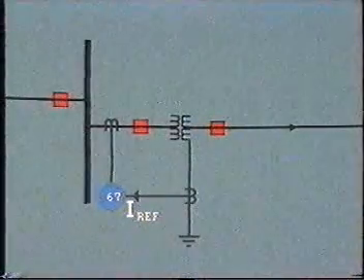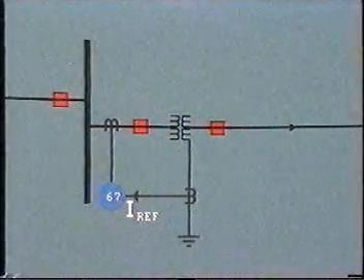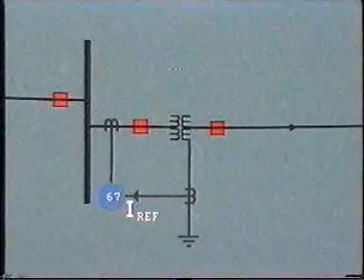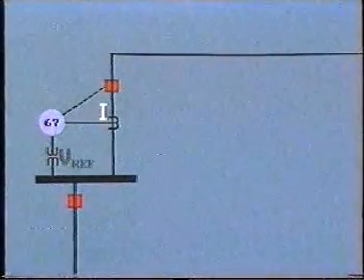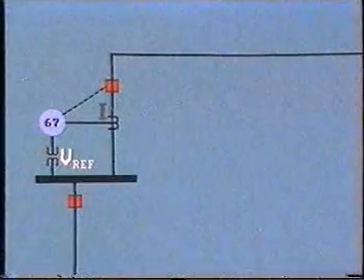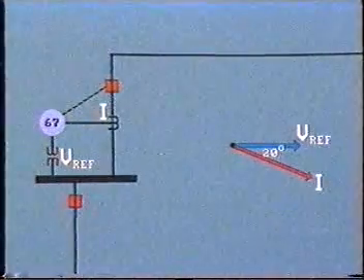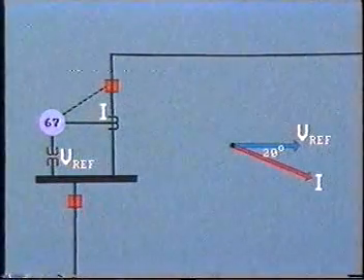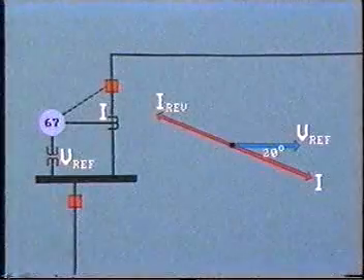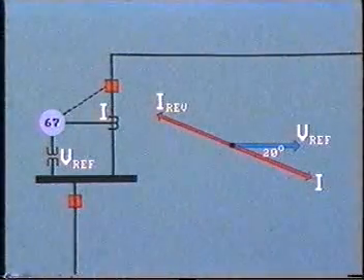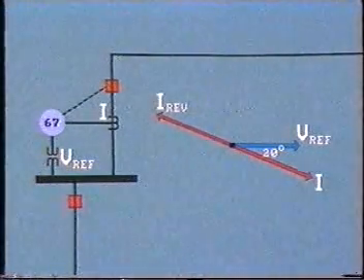For example, if current is used as the polarizing quantity, it can be obtained from a CT located in the grounded neutral of a Y-connected transformer. In this simple arrangement, the directional element receives reference voltage from the VT on the bus, and current is measured by the CT in the protected line. In normal operation, the phase angle of the current may be up to, say, 20 degrees lag. But if the direction of current flow reverses, the phase angle will change by 180 degrees. This very large difference is easy for the relay to detect and activate the directional element.